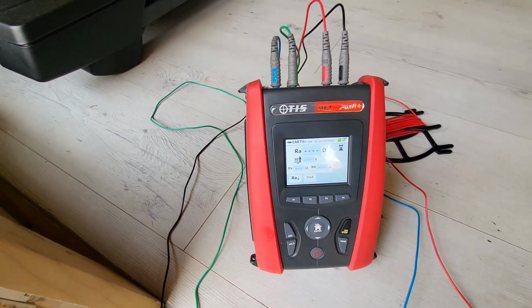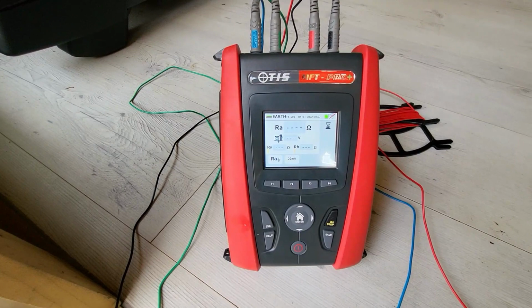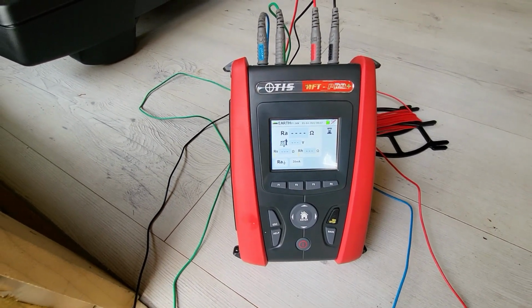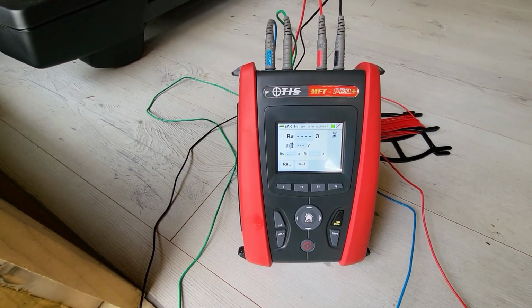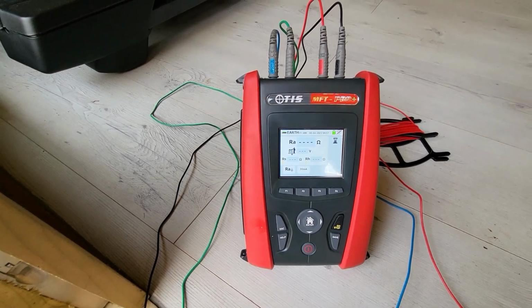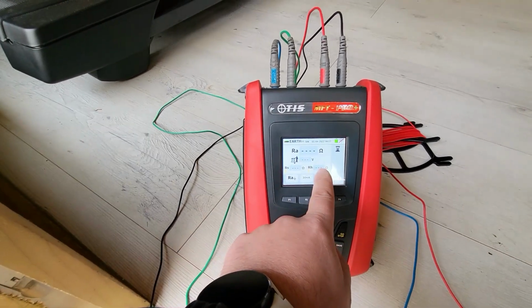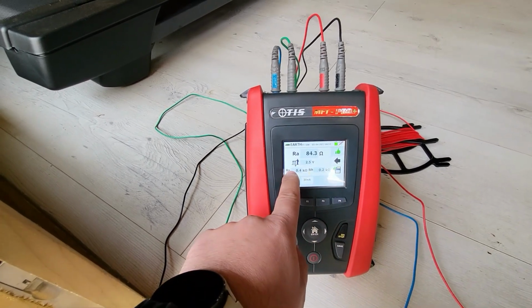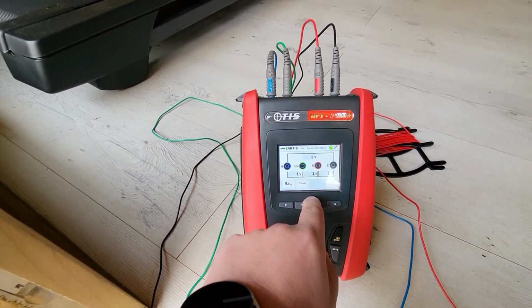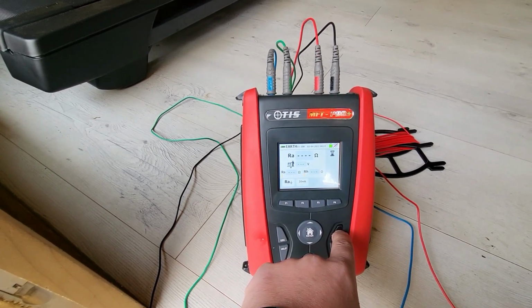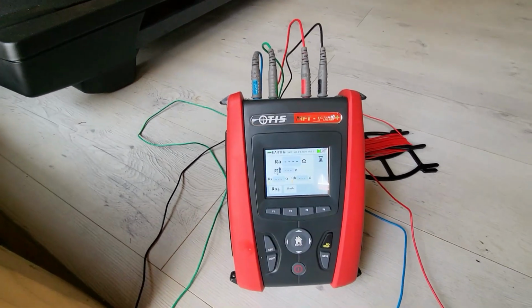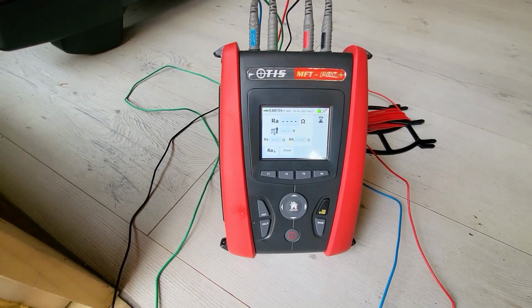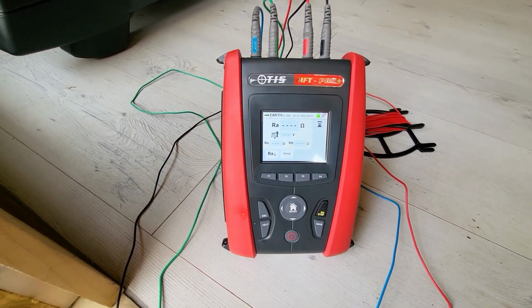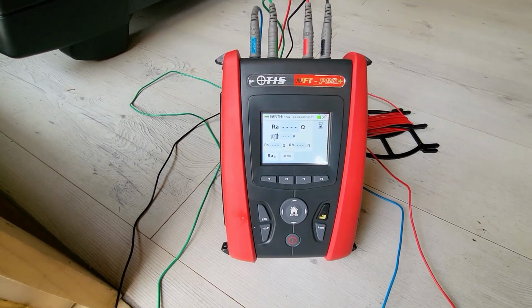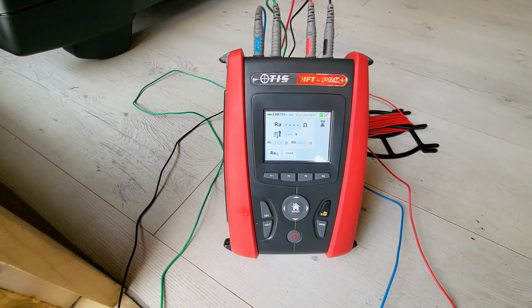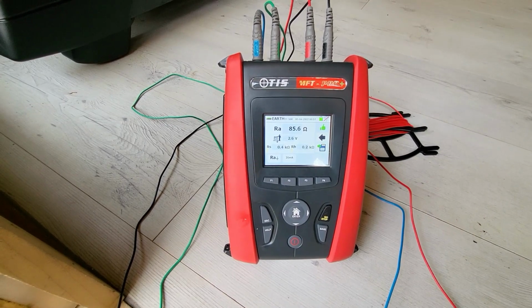If I hit the test button, it's now going to carry out its little magic calculation between the current spike, the voltage spike, and the actual clamps onto the electrode itself. It will give us a resistance value to that current spike, to the voltage spike, and then an average of the electrode resistance for RA. So it's actually given us some extra information with the TIS MFT Pro Plus that some other multifunction test instruments don't give you, and it's insightful just to see the value of impedance to those prongs themselves.